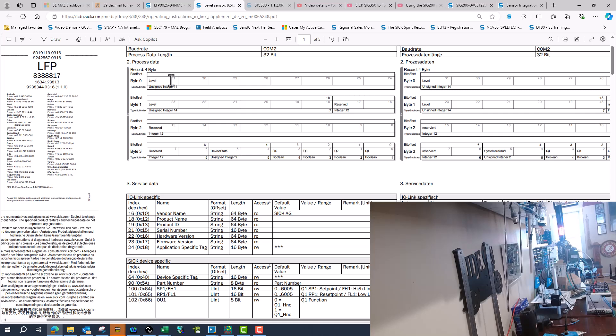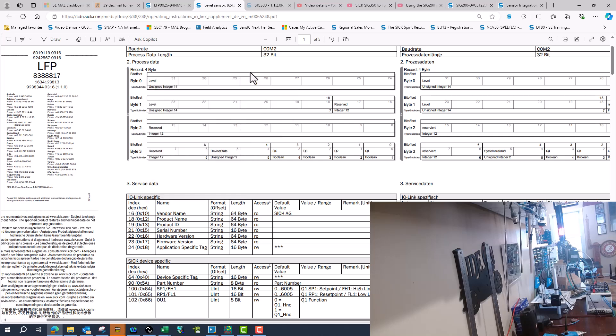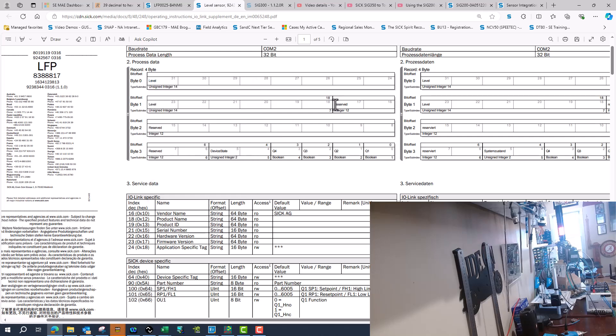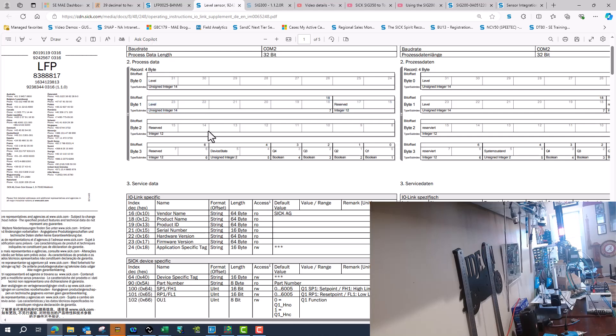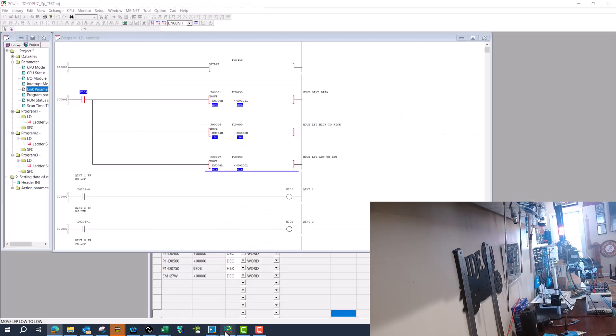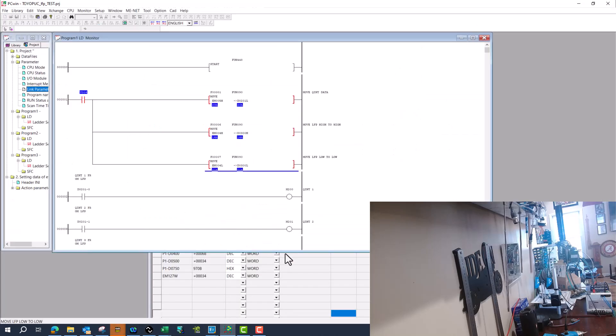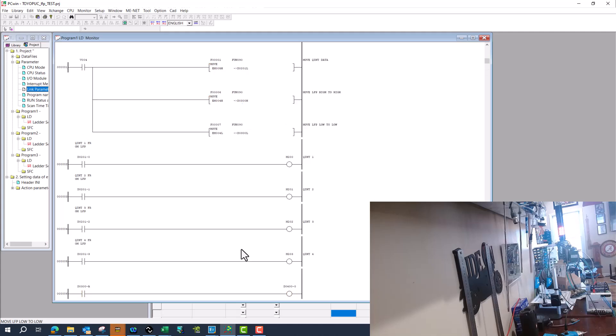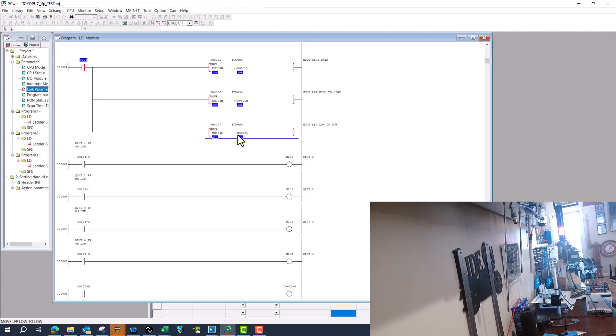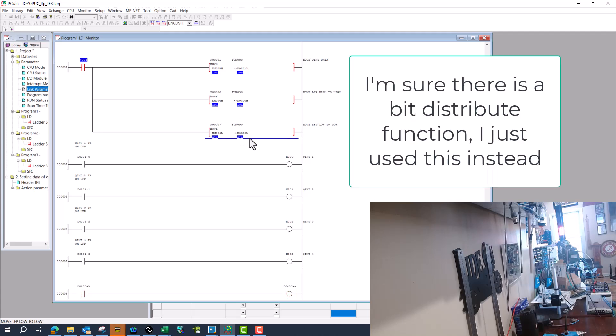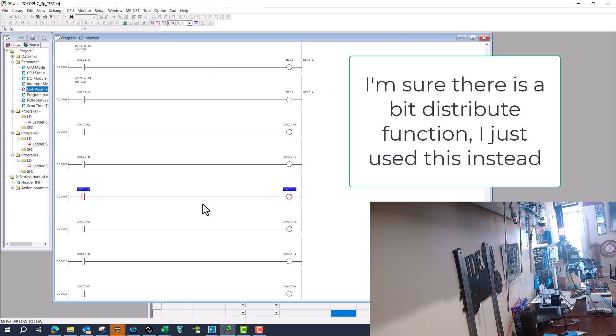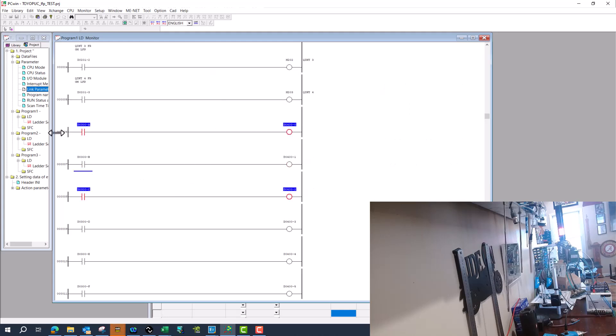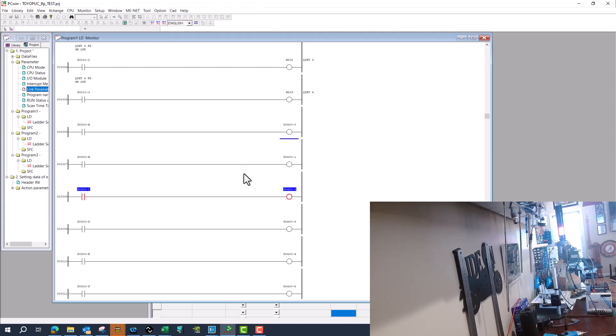So we get two bytes of data that is the level. But at the same time, you see these right here. So it's not 16 bits. It's a 14 bit unsigned integer that comes in. So to get that data to look correctly in the PLC, I had to rearrange it. So you can see that I'm taking EM004 to D300. And then I'm taking that data here, and I'm just breaking out those bits, and I'm transferring them over to get rid of those other two that we had. So I took those 14, and I made another word. So now it's D400.